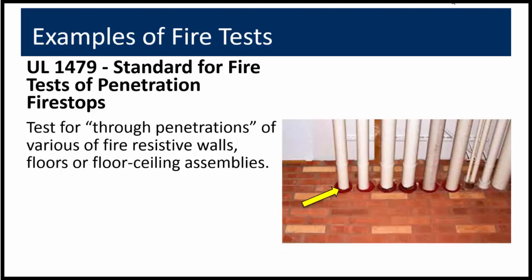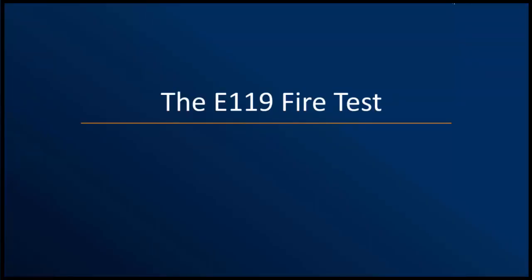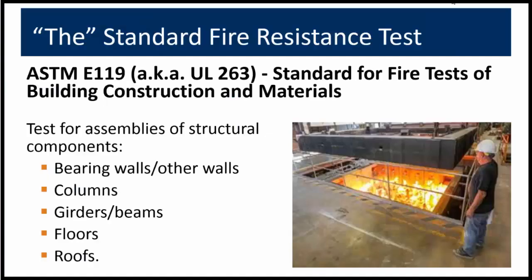I have often encountered data supplied by vendors which was not relevant to the use of the product. Now we're going to focus on the very important fire test applicable to fire resistant rating of building structural elements, what I call the father of the fire test regime, often referred to as the E119 fire test. The ASTM E119 test is the place where the standard time temperature curve resides. It's the fire test that applies to assemblies of structural materials for buildings, including bearing walls, other rated walls, columns, girders, beams, and assemblies for floors and roofs.